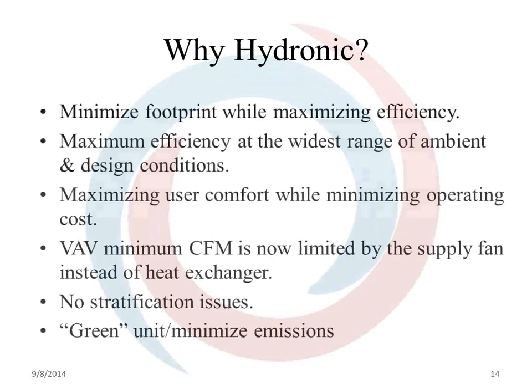Now, why hydronic? Well, as we all know, water holds more energy than air, so it's a better medium to transfer heat. You can transfer the same amount of heat in a much smaller surface area than air to air. Plus, user comfort is not just for the occupants. In factories or processes that require a specific temperature to be maintained, Xcelon can maintain a specific constant air discharge temperature to within plus or minus 0.5 degrees. Let me repeat that. Xcelon can maintain a constant discharge air temperature to plus or minus 0.5 degrees. Again, scaling with the competition units, they can't hold that.